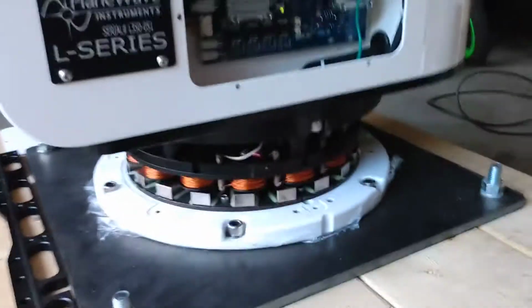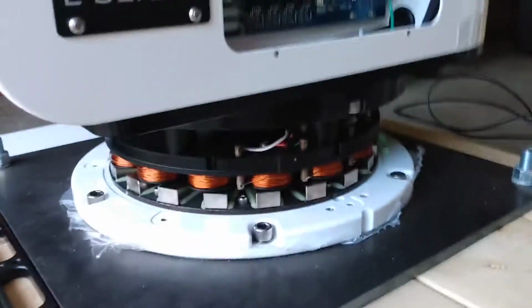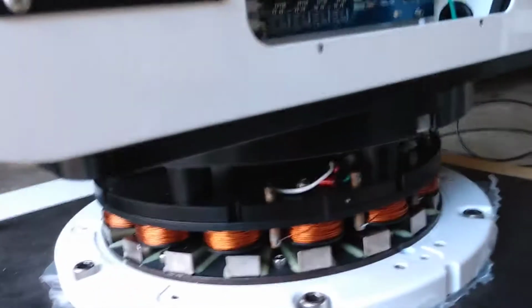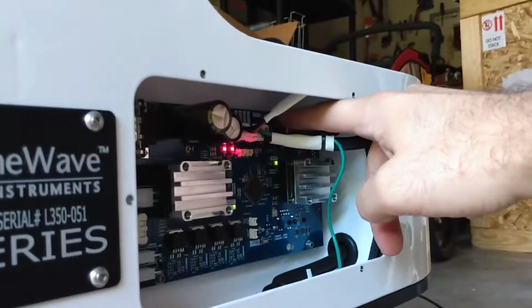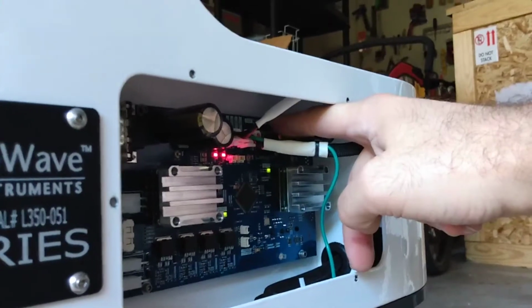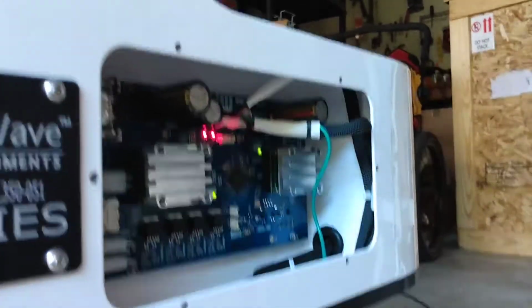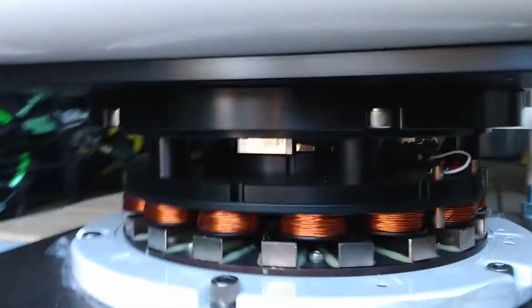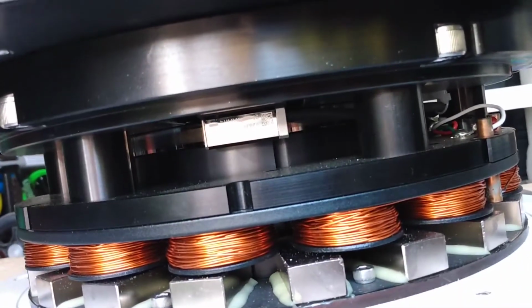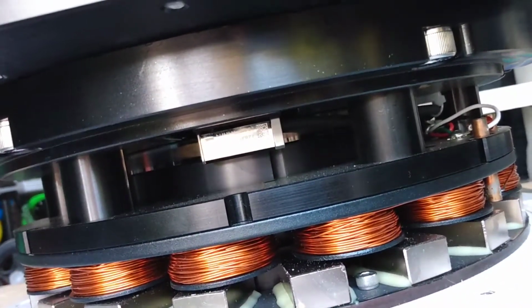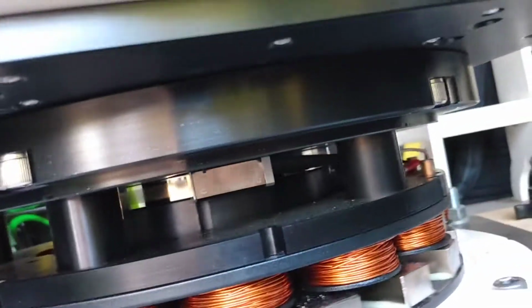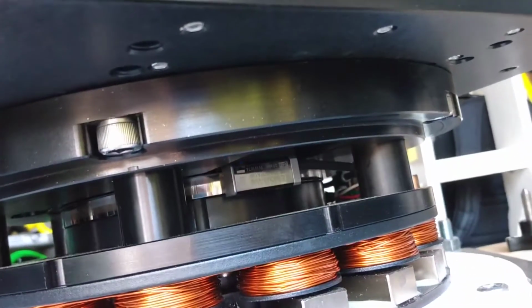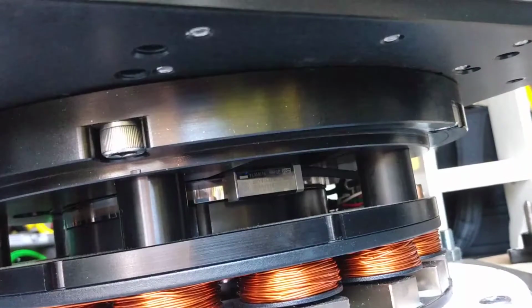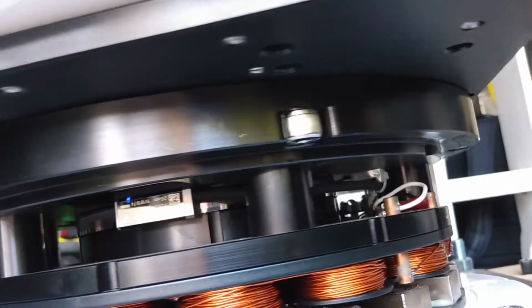Now, if you ever find that the index mark is not reading out correctly and homing is failing as a result, the easiest way to recalibrate the index mark is to press the calibration button up here for about half a second. Just press, hold, and release, and you'll see that the light on the read head is now flashing about once per second. Move the axis by hand until you see the encoder flashing twice every second, and then go back and cross the index mark.